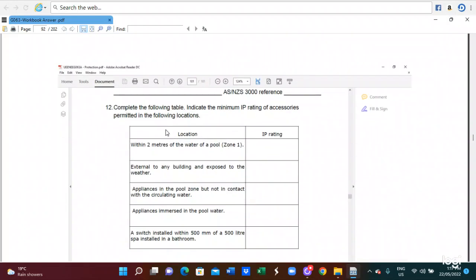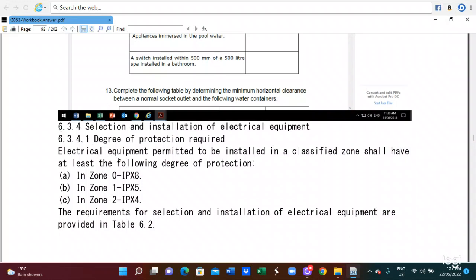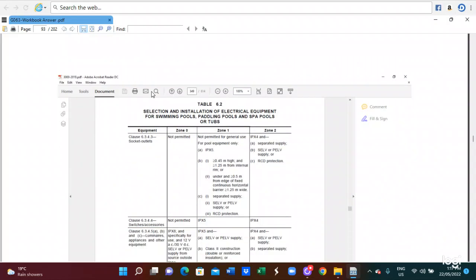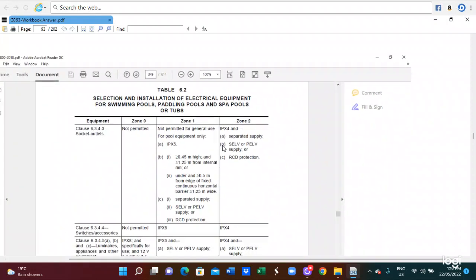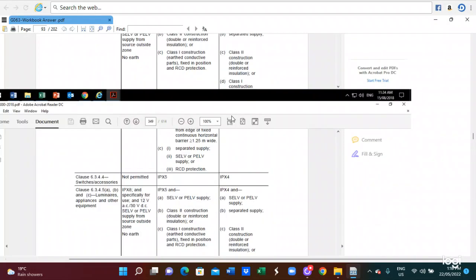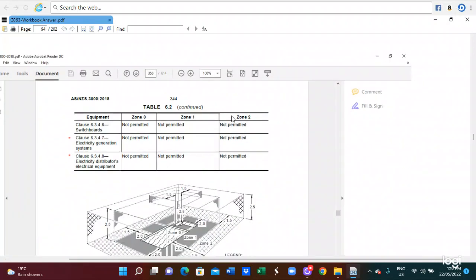In the meantime, this is for the location and the IP rating. So for this location IP rating you have to read clause 6.3.4.1, the protection equipment and appropriate IP rating system. Also you need to follow Table 6.2, selection and installation of electrical equipment for swimming pool, paddling pool, and a spa pool or tub. So we have to refer to Table 6.2. And also with Table 6.2, you see Figure 6.15 of the AS/NZS 3000, 2018 edition.